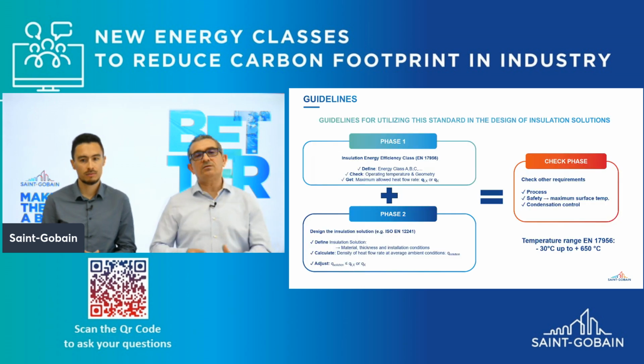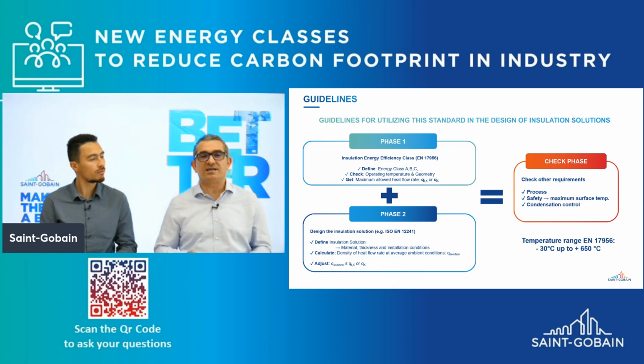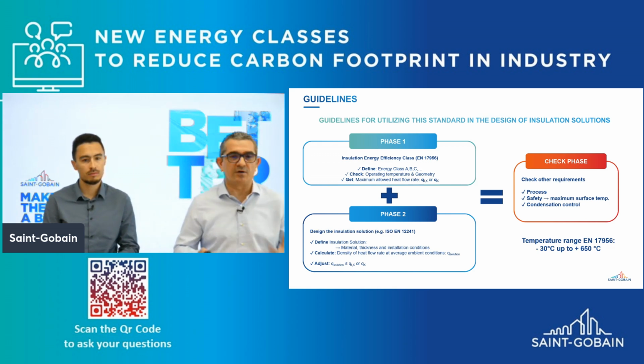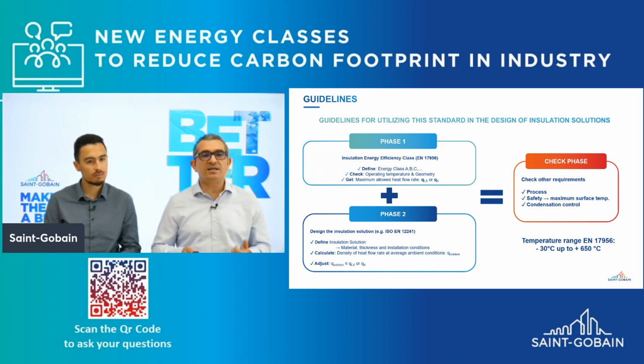This is a new procedure to calculate or propose insulation solutions. Until now, we have used only the ISO standard 12241, and now we have to introduce some calculations beforehand with this new standard. In phase 1, it's necessary to define what type of energy class we need: A, B, or C.